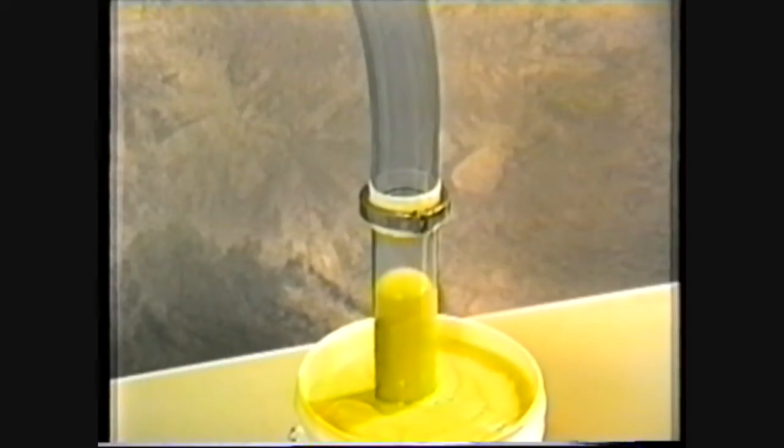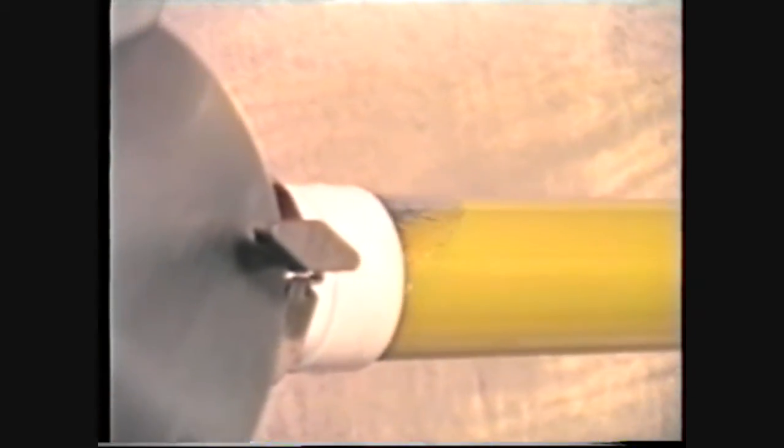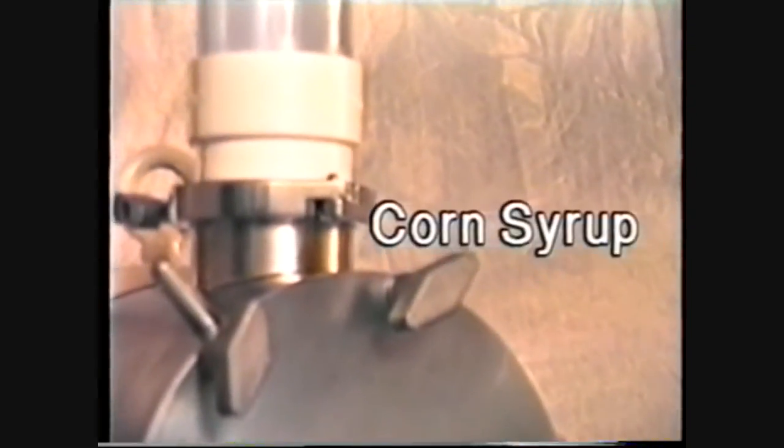Due to the close tolerances of the internal components, Sine Pump is capable of lifting 29 feet of water or generating 26 inches of mercury vacuum. With this powerful suction capability, Sine Pump can handle a wide range of viscous products such as corn syrup, meat emulsions, cookie fillings, concentrates, and lotions, and is ideal for tanker, drum, and tote unloading applications.